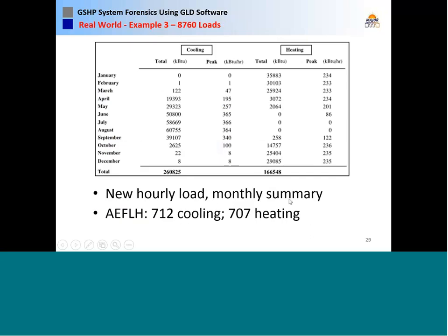We ran a new hourly load profile and came up with what we felt was a reasonable load calculation. This is right off of GLD's zone manager, the monthly summary for the hourly loads.